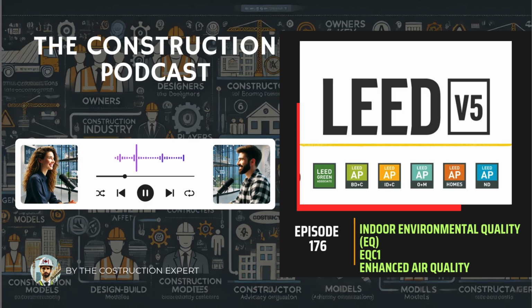And again, just like with option 1's increased volume, these high-efficiency filters introduce their own significant fan energy penalty. They create more resistance to airflow, meaning the fans have to work harder, using more energy, just to push the air through. So here you're trading the energy penalty of dilution, option 1, for the energy penalty of extreme filtration, option 2. Okay, so PM2.5 at 10 µg/m³ means serious filtration and the energy that comes with it.